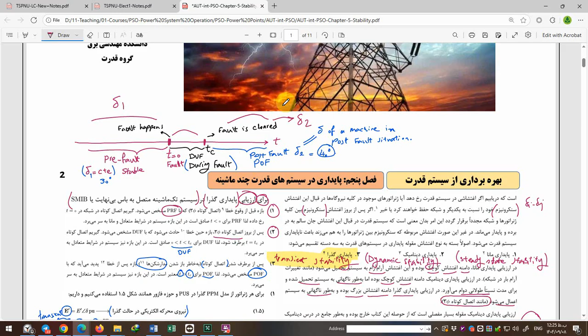In pre-fault we have a delta, for example delta 1. During the fault the delta changes or oscillates, and after the fault we get delta 2. If delta 2, or the second situation of delta, is fixed, it means your synchronous generator is stable. If delta 2 oscillates, or gradually increases or decreases, it means your generator is unstable.